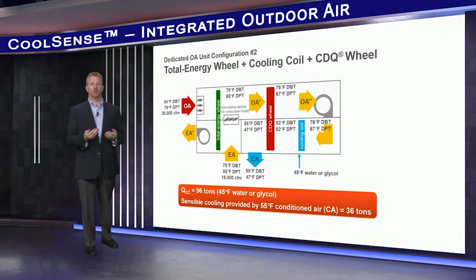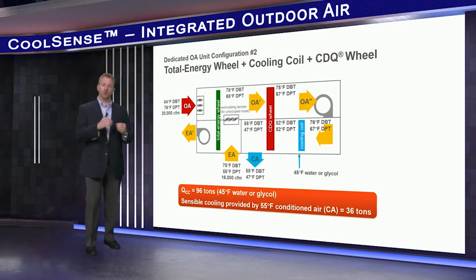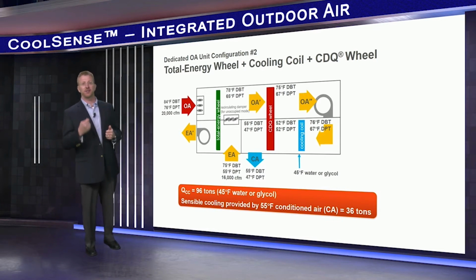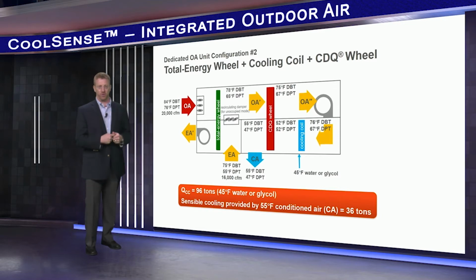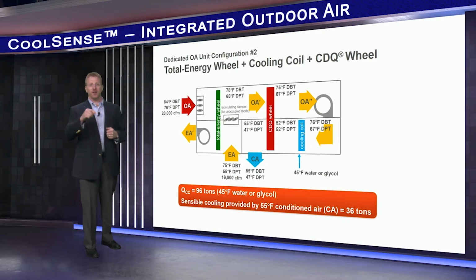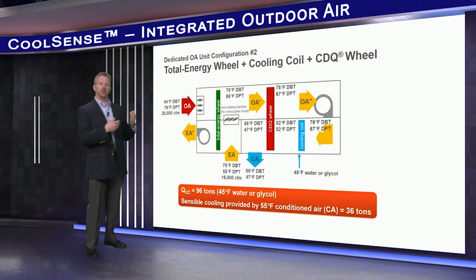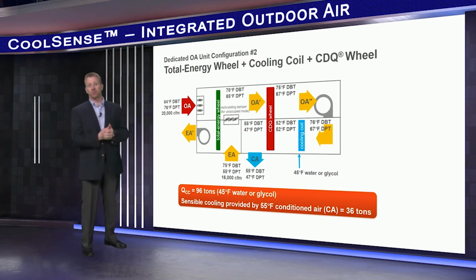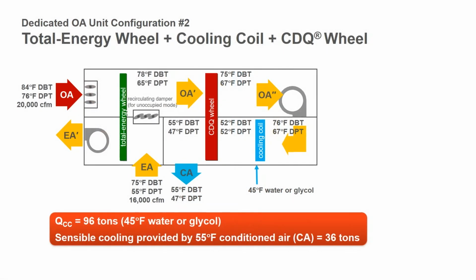Now let's move on to the second unit configuration. I've gone back to this single cooling coil, but now I've added a desiccant dehumidification wheel in series with the cooling coil. That is, one side of the wheel is upstream of the coil and the other side downstream. This is Trane's branded CDQ technology. This configuration offers some significant advantages. First, since the desiccant wheel provides further dehumidification downstream of the coil, the cooling coil requires only 45-degree water to achieve the required 47-degree leaving air dew point. And in this case, the required cooling capacity drops to 96 tons compared to the 107 in the first configuration.